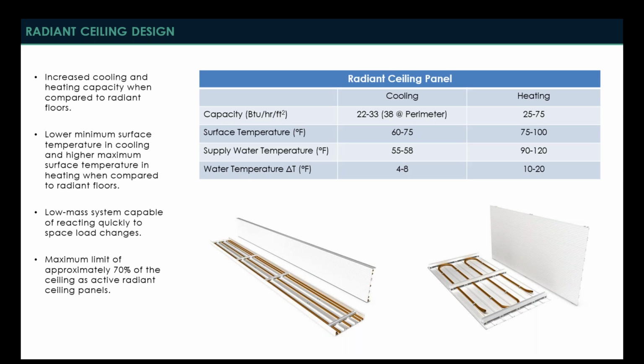You can see that the surface temperature minimums and maximums are a little bit different than we were looking at with the floors, and it makes sense because if you have more capacity, you probably have a higher temperature surface. So for most cooling applications, we want to limit that temperature to around 60 degrees at the surface, and in heating around 100 degrees. Sometimes if you have a very low ceiling, that heating number may need to come down. So you really have to analyze all of the physical aspects of the space to figure out what my ideal temperatures are going to be.